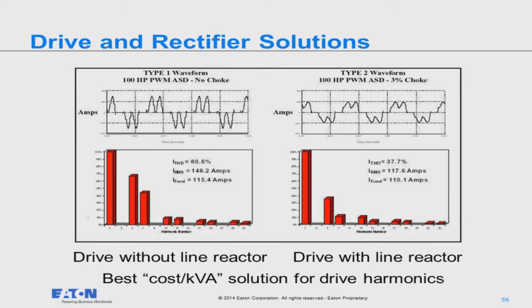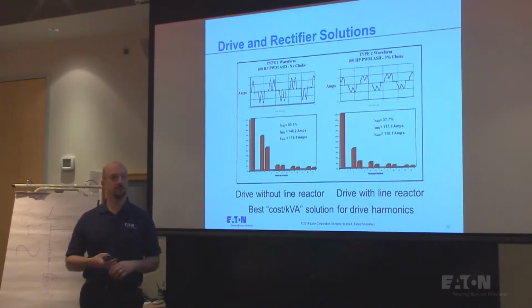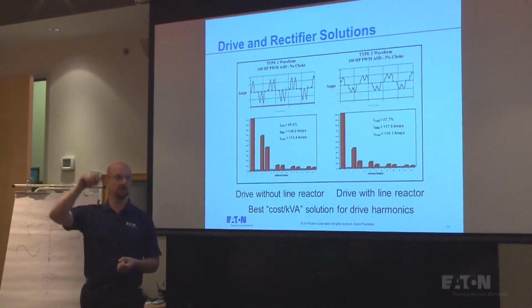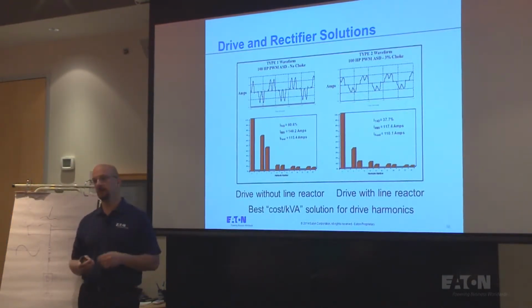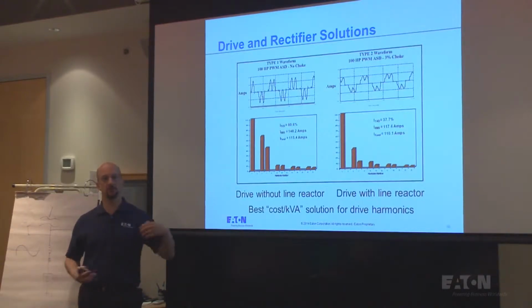So here's the thing, Adrian already showed you a little bit about this, but this is actually out of the IEEE standard, and it basically shows a 6-pulse drive with very little impedance. Really what they're saying is you need a little bit of impedance to make the thing work and not blow up. But a capacitor on the DC bus of a drive, capacitors don't like to instantaneously change voltage. So the capacitor is going to draw a current that's very, very steep. It can change current as quickly as it wants, right? Except for the fact that you have an inductor in front of it. If you have a choke, an inductor, an AC or DC bus reactor, it's going to slow that current down. And so when you have those two elements competing with each other, current doesn't like to change instantly through an inductor, voltage doesn't like to change instantly through a capacitor, you kind of have to balance that out.